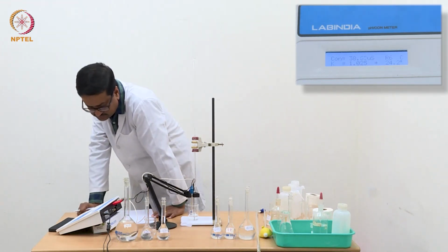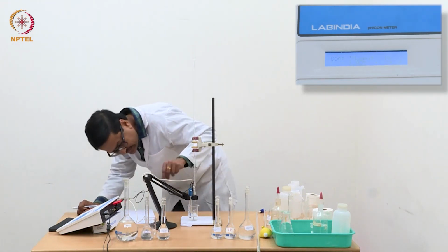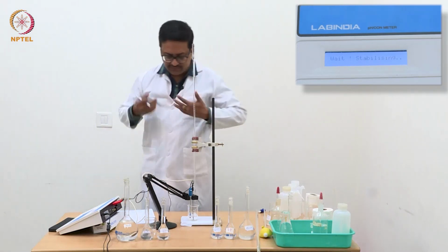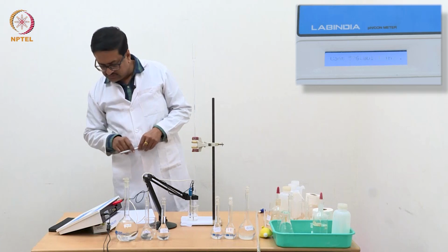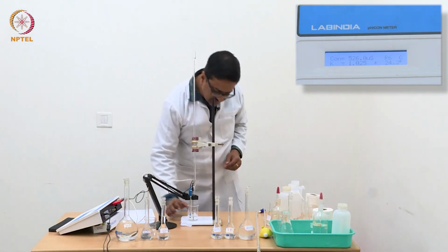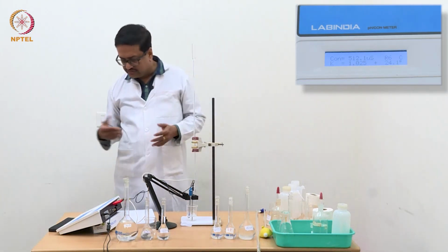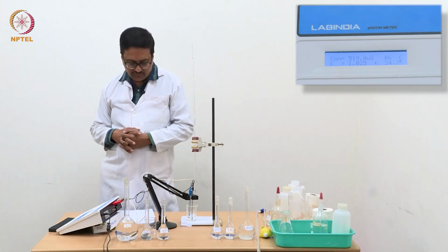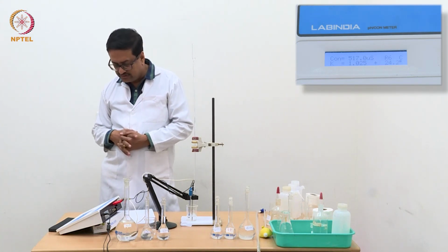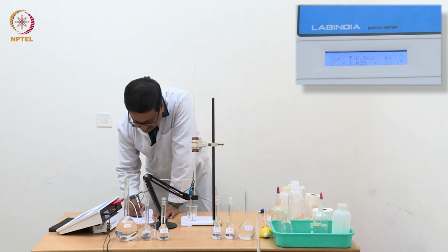What happened? It is not reading. Yeah, so the electrode was above the water level, so it was not reading the correct value. We should wait for it to stabilize and homogenize as well. So then you know that we are close to the neutralization point.